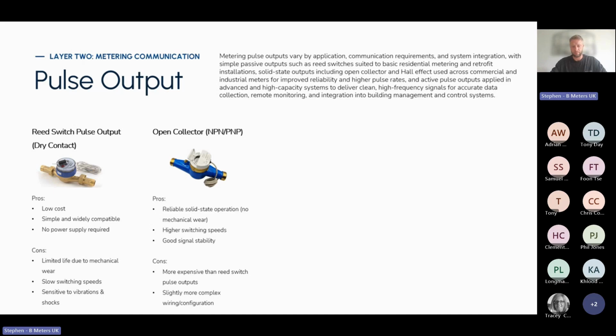Open collector pulse outputs are much more robust. They have higher switching speed, good signal stability, and reliable solid state operation. The downsides really are installation and commercial. Because there is more functionality, there's more to it, and they're more expensive than reed switch pulse output. They're also slightly more complex in terms of wiring and configuration. For example, our PL3s have an app where you can set the pulse values. It works via NFC. It can be a bit fiddly, but it's nice and easy to set up. And the difference is you just have to get the polarity correct with which cores you're using.